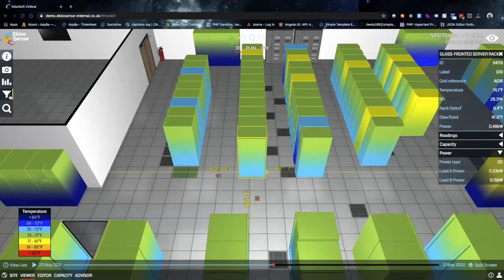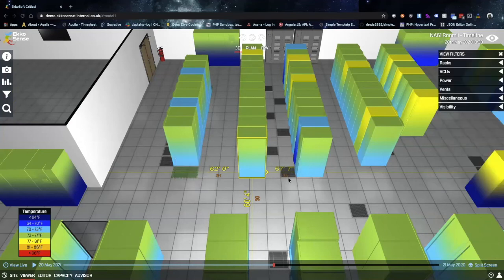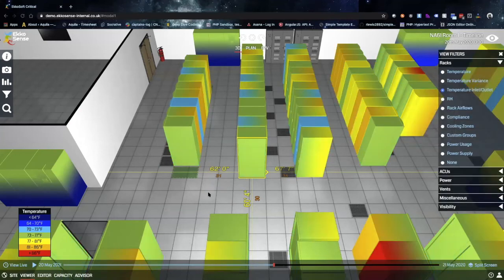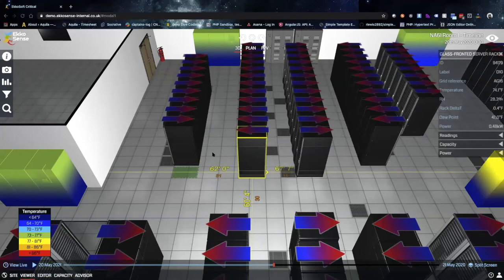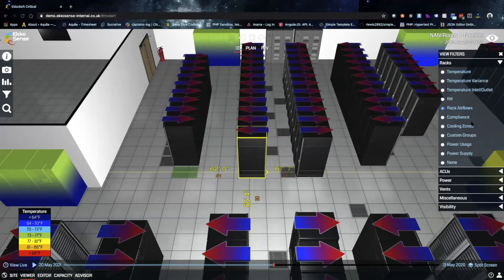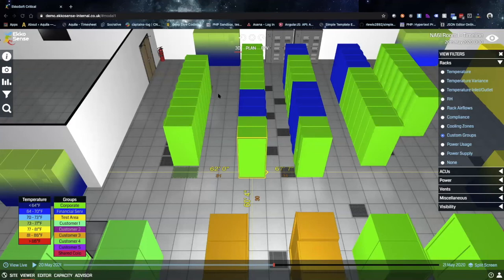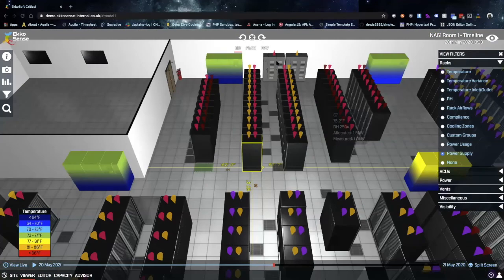So since this is built on a gaming engine, we're able to really see a lot of the data in a much different way than other solutions provide. So we can go into what we call the filters. For example, for the racks, we can visualize the inlet and outlet temperature differences. We can look at the rack airflows to make sure that everything's positioned how it should be. We can look at the compliance, for example, custom groups. So let's say an end user has racks that have different compliance levels. We can go ahead and specify this here, or for co-location facilities, for example, we can go ahead and split those up. Then we can look at power supplies. So you saw this graphic in the slides. So we can just see exactly what power sources this rack is actually being fed from.